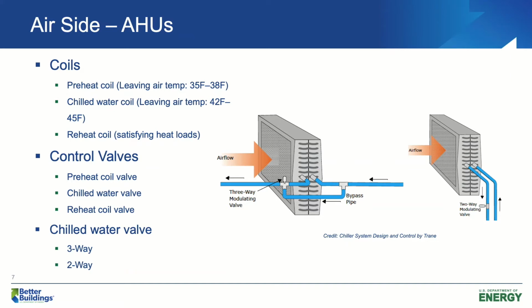We also have three coils inside air handling units. We have preheat coils, chilled water coils, and reheat coils. The purpose of preheat coils is to warm up the air a few degrees above freezing point. This way, the cold air will not freeze and damage our chilled water coil in winter. The chilled water coil is our main coil. The chilled water coils make cool and dry air. Sometimes we also have a reheat coil. The job of reheat coils is to add heat to the airstream so we can satisfy the heating load of our spaces. For these coils, we have some control valves.